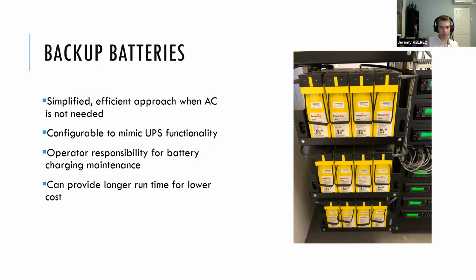But with that obviously comes the responsibility for charging and maintaining the batteries. That was done automatically in that UPS. Now, if you've just wired up a battery bank for yourself to use, it's on you to make sure it's effectively wired for charging and for maintenance of those batteries so it can be ready when you need it. And as a cost comparison to a UPS, you can get a lot more effective runtime, higher load if you're going direct to battery, because you're eliminating that conversion. You're eliminating a lot of the sensors and technology that was needed to give you reliable AC support, simply because we can operate at that DC level.